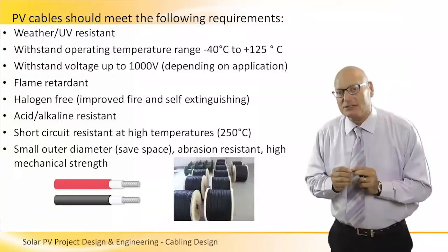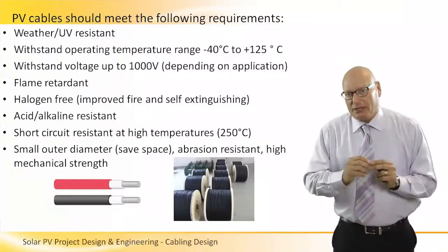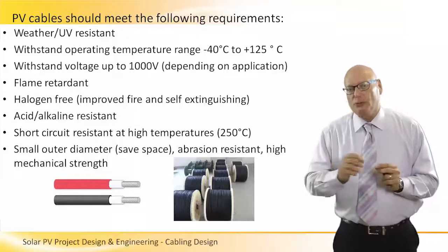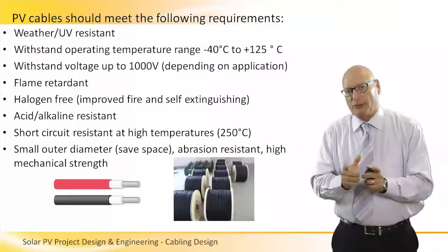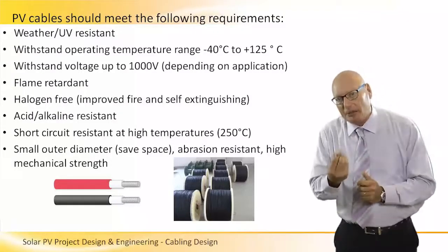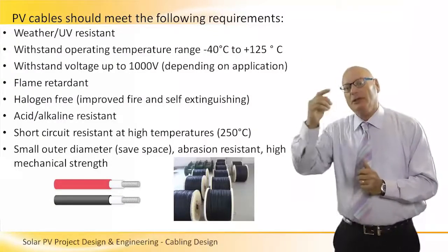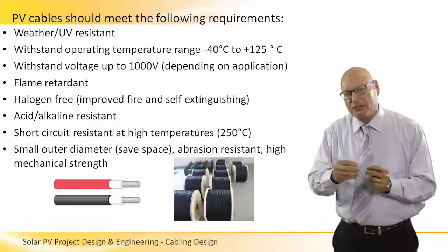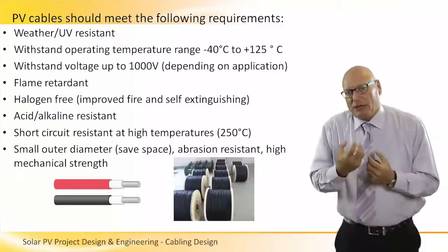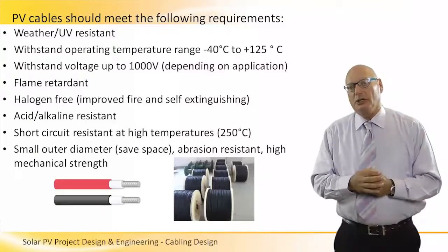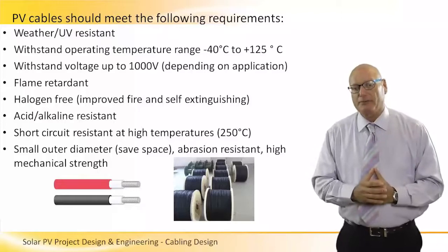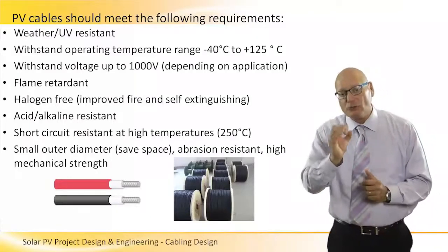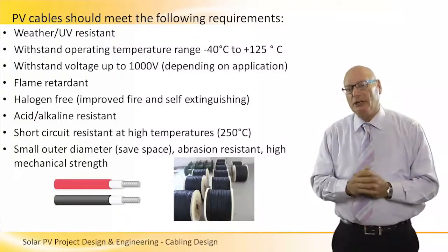The cable should also resist acid and alkaline, and have short circuit resistance at high temperature — 250 degrees C. Short circuit resistance means that when we have a short, which is a spike of very high current over a very short amount of time, a pulse, that cable should withstand that even in very high temperatures, because that spike with a tremendous amount of energy creates tremendous heat. It should also have a small outer diameter in order to save space.